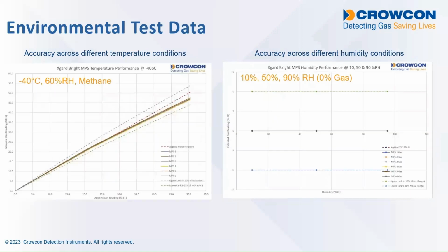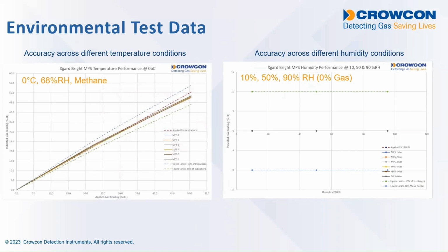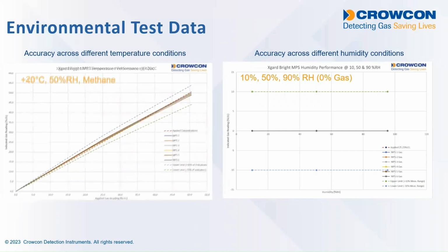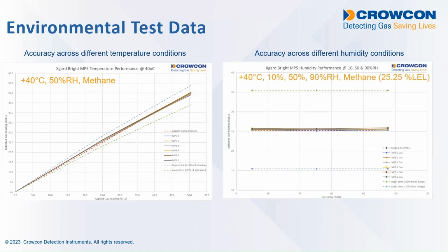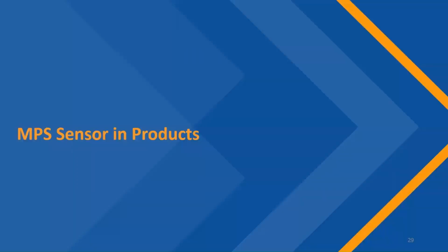And in environmental tests, you can see that we've exposed sensors to gas at minus 40 degrees Celsius, minus 20, 0, plus 20 degrees Celsius, and plus 40 degrees Celsius. And the response remains consistent and accurate. And that's because of the temperature compensation in the sensor. And again, changing humidity from 10% to 50% to 90% relative humidity results in consistent readings from the sensor as well. So environmental effects changes are very accurately negated in the algorithm of the sensor.